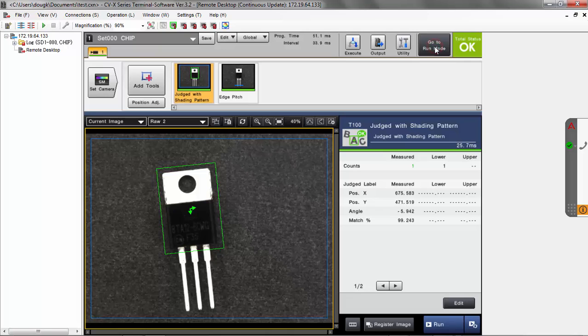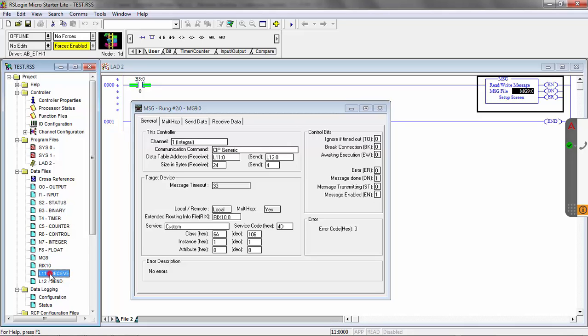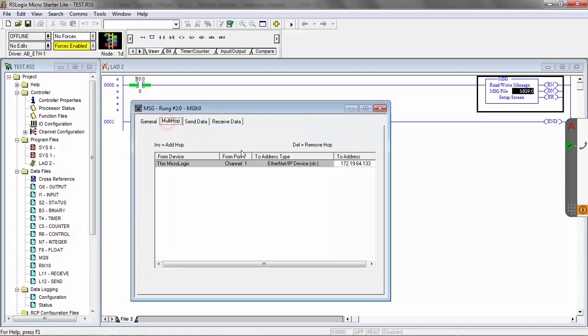Let me put this back to run mode and go back to our message setup on the PLC side. We're going to receive 24 bytes of information, and we're going to receive that into L11 — that's our receive data location. Set up your receive information and how many bytes to receive based on what you set up in the CVX output section. We're always going to send 4 bytes from L12. The MultiHop tab is where you put the IP address of the CVX controller, and we're going to send this message to that IP address.